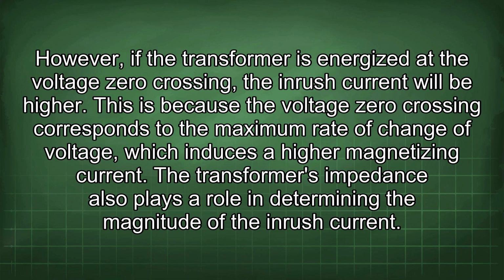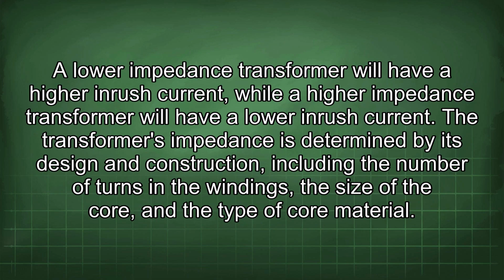The transformer's impedance also plays a role in determining the magnitude of the inrush current. A lower impedance transformer will have a higher inrush current, while a higher impedance transformer will have a lower inrush current. The transformer's impedance is determined by its design and construction, including the number of turns in the windings, the size of the core, and the type of core material.